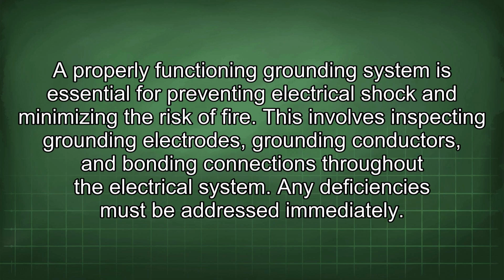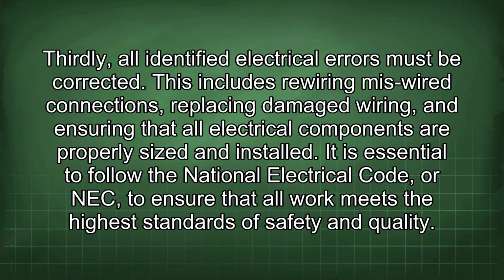A properly functioning grounding system is essential for preventing electrical shock and minimizing the risk of fire. This involves inspecting grounding electrodes, grounding conductors, and bonding connections throughout the electrical system. Any deficiencies must be addressed immediately. Thirdly, all identified electrical errors must be corrected. This includes rewiring miswired connections, replacing damaged wiring, and ensuring that all electrical components are properly sized and installed.